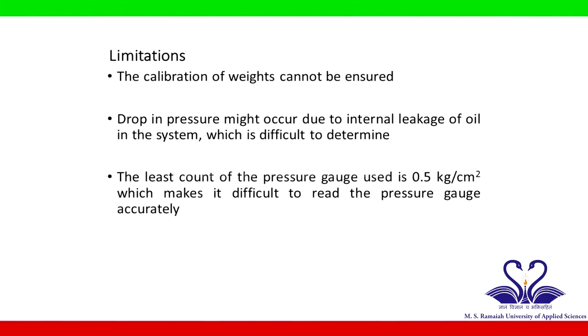This experiment has its limitations. The calibration of weights cannot be ensured. Internal leakages might occur inside the system which are difficult to determine. These leakages may lead to a drop in system pressure, which leads to wrong readings. The readings cannot be taken accurately as the least count of the pressure gauge being used is 0.5 kg per centimeter square. This concludes the experiment calibration of a pressure gauge using dead weights pressure gauge tester.